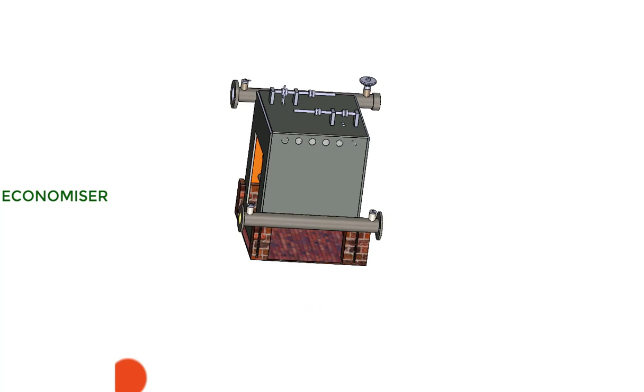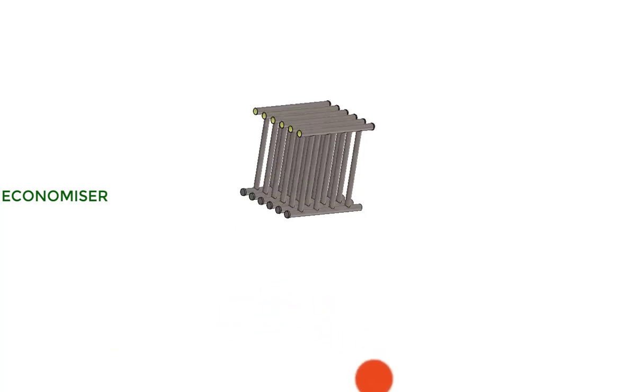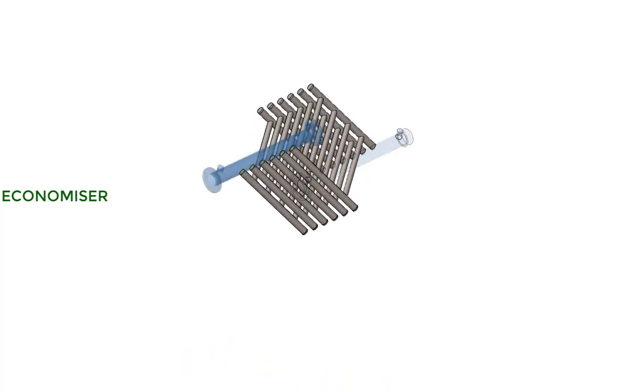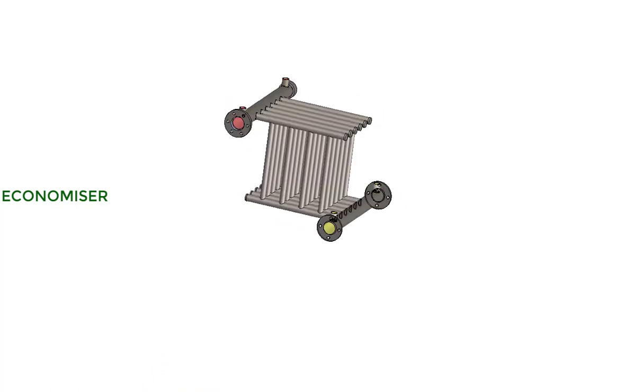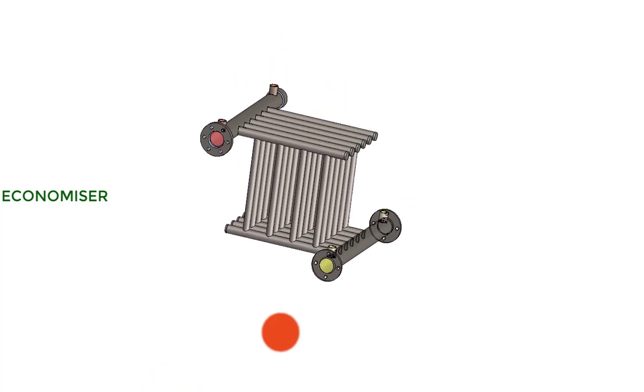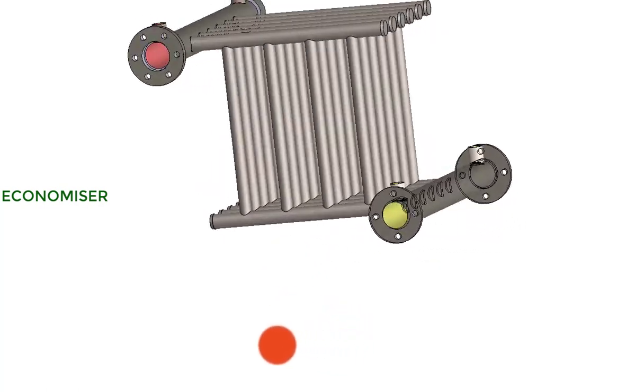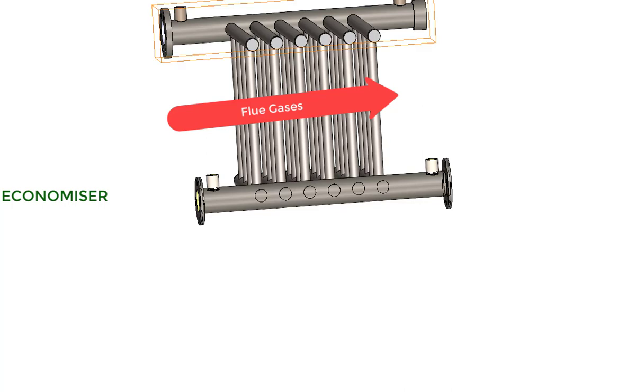The hot gases move across the vertical tubes. There are also horizontal tubes — these can be called sub-headers — which are connected to the main headers. These are the two main headers: one top header and one bottom header. Water moves from bottom to top through the vertical tubes, which are exposed to the hot gases passing from the combustion chamber to the chimney.